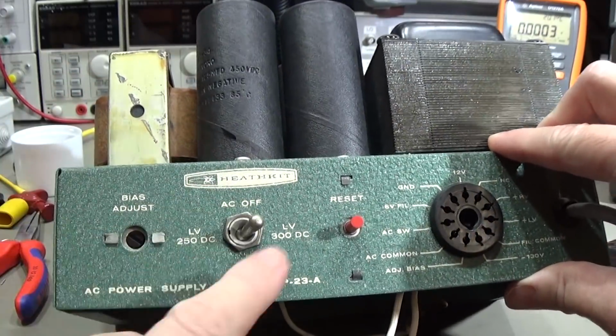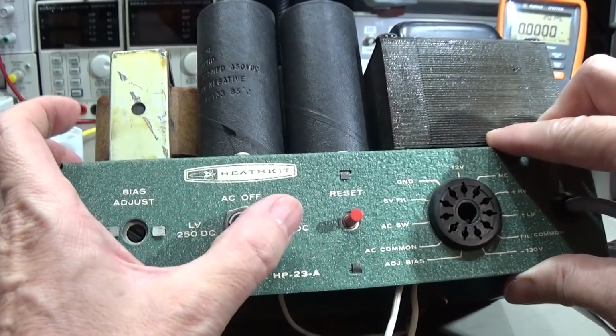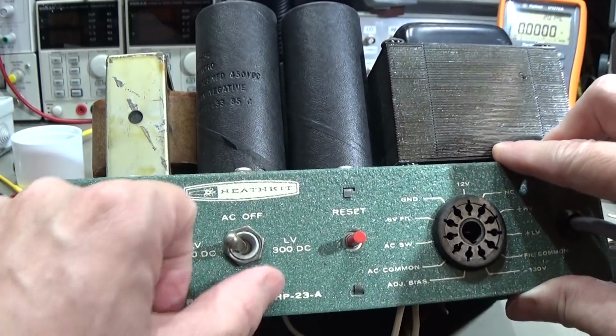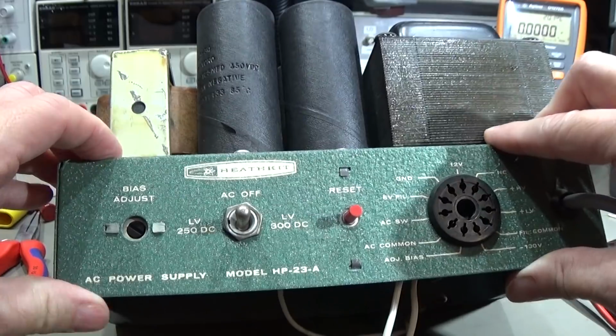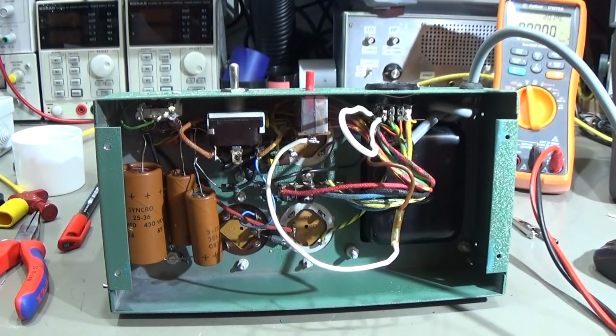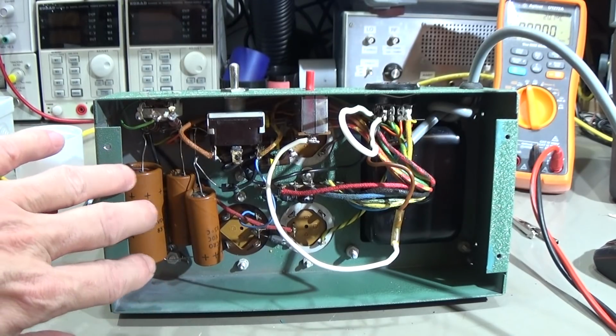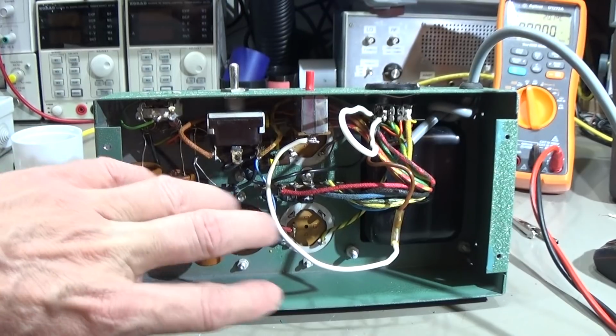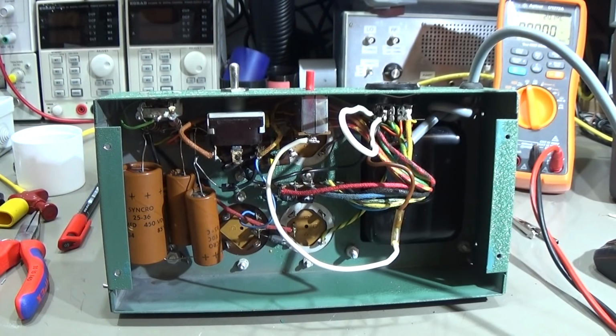First, we recognize that we're missing the 300 volt DC, whereby we do have the 250. Then we recognized there's a kind of load where we don't know where it's coming from. A short check of our capacitors showed they were not bad. We tested the ESR and didn't find anything special, but that could still mean the capacitors are leaking, which would explain the load.